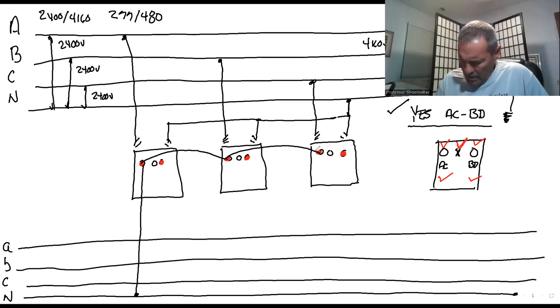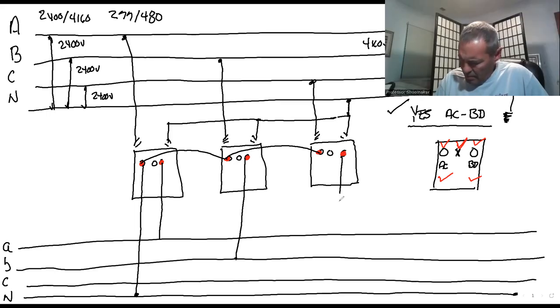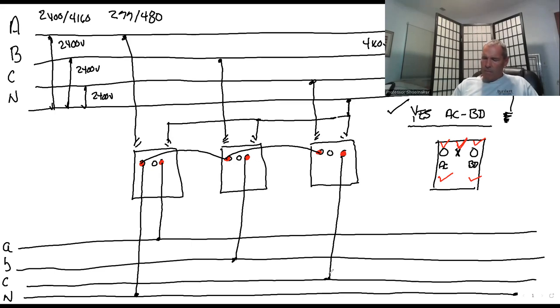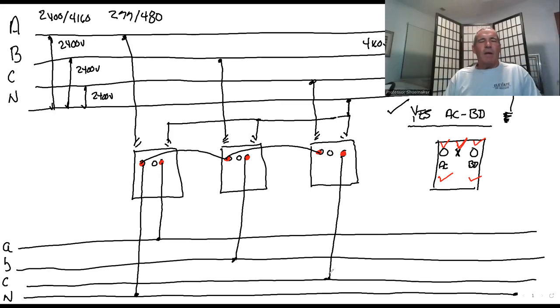All right. Here's the fun part about it. What's left? A, B, C. B, sure, go to the right line here. And C. Wiring's done. Now all I have to do is draw in my secondary voltages. So you'll notice here, there's no lighting, no high leg in Y, right? Right. So it's A to N, B to N, C to N.